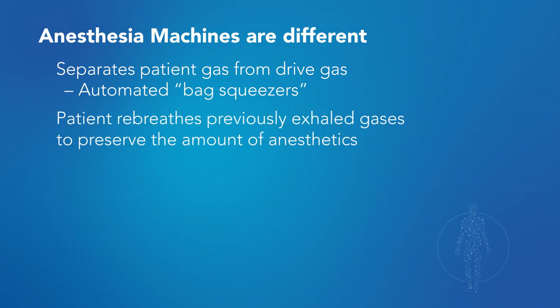In all anesthesia machines, there's an attempt to have the patient rebreathe some of the gases they previously exhaled, in order to preserve anesthetics and not use too much. In the operating room we conserve anesthetics using techniques called low flow. But in the ICU that's not a good idea, because over long durations the anesthesia machine starts to have problems with humidity buildup and consumption of disposables becomes a problem.